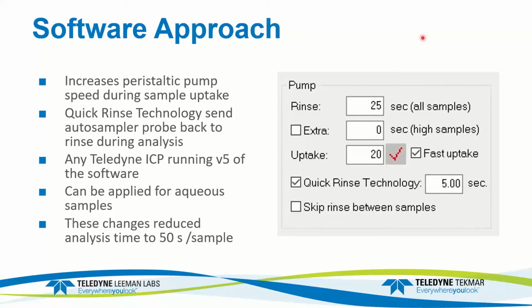So during the software approach, what we do is we increase the peristaltic pump speed during the sample uptake. There's the ability to change that. We ran this one at approximately 85 RPM. Maximum is 200 RPM. So if we wanted to increase the speed even more, we could do that by increasing the speed of the pump on uptake.